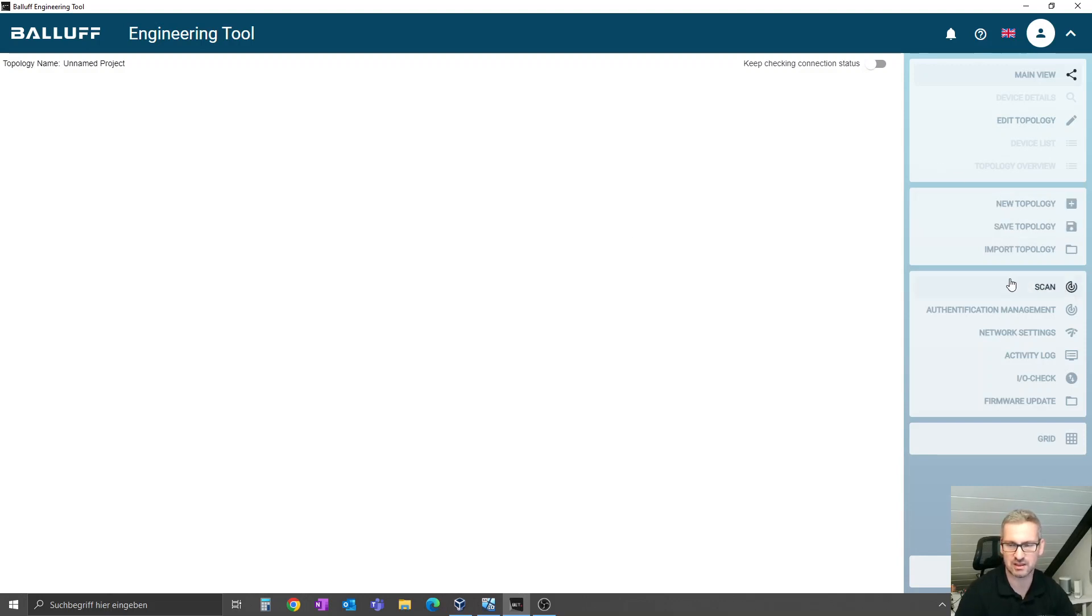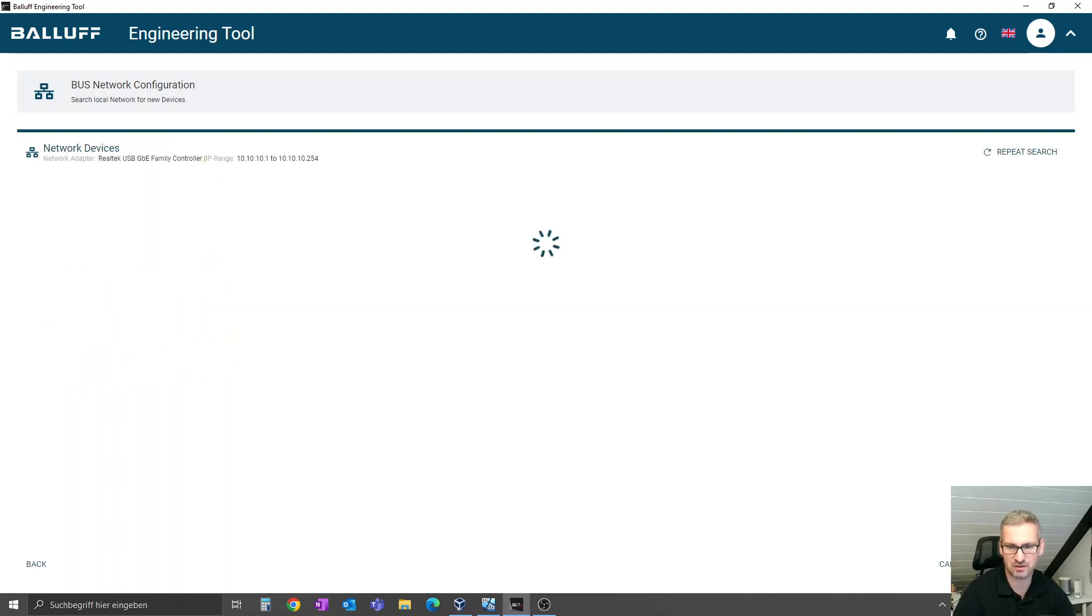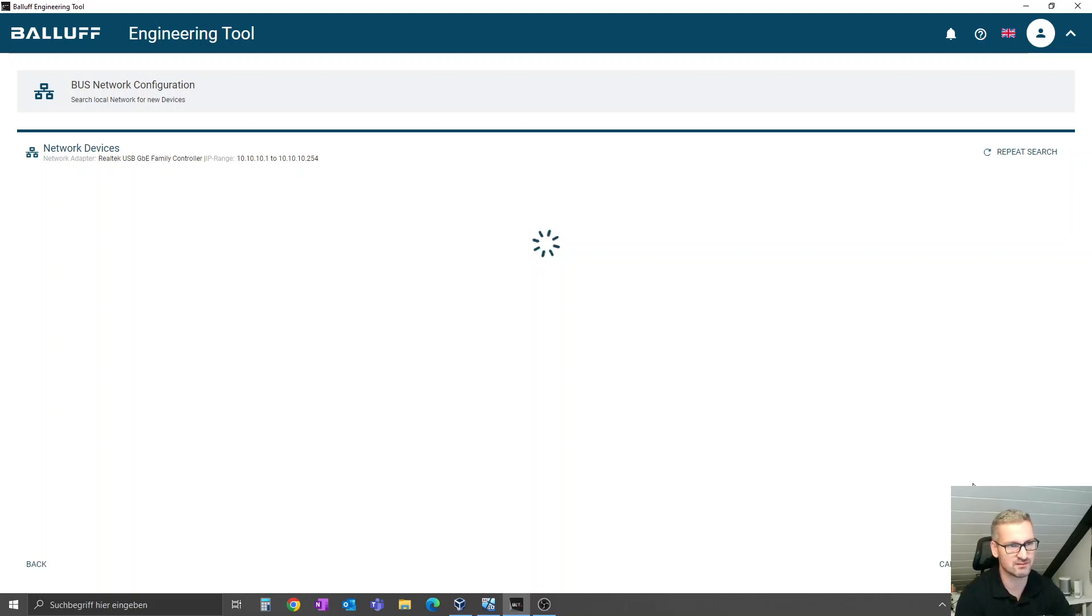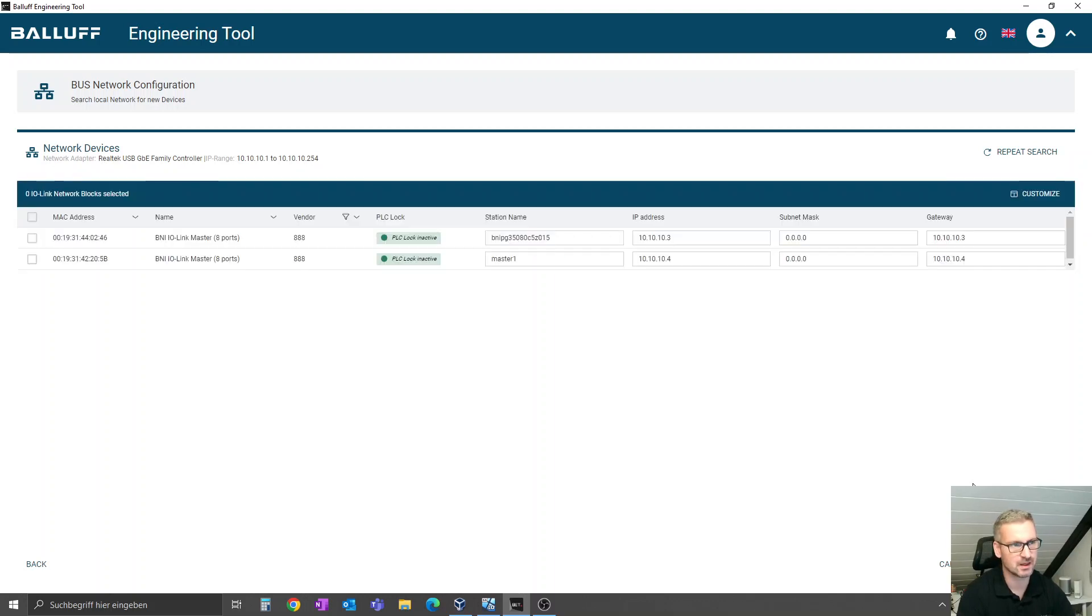The network settings are the first step. You can discover your different network controllers. In my case, I have this one. Click here on the right corner, scan for devices, and then the system will discover the connected network devices and show you in the list what it found. Then you can adapt the Profinet name, the IP address, and so on, and then proceed with the further steps.